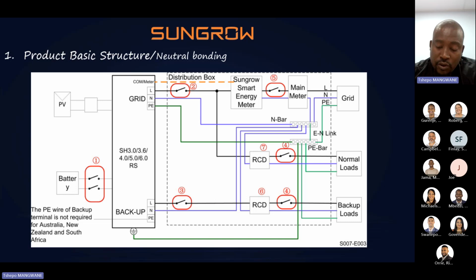In an event of load shedding, the inverter cannot break and restart if the neutral is bonded. If the installer does not bond the neutral and earth, should the main grid switch off, the inverter will restart. So make sure that they bond their neutral. I'm just looking here: the earth from the backup solution goes to the bar when the grid side goes, and then the neutral is also bonded there.